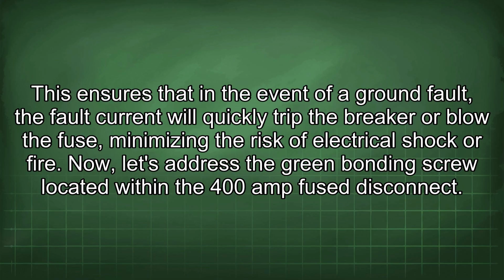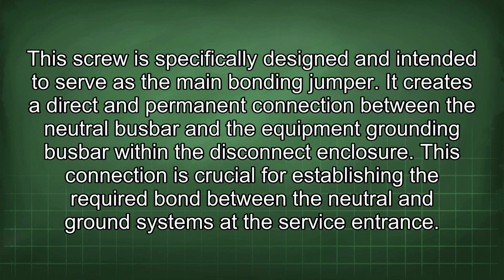Now, let's address the green bonding screw located within the 400 amp fused disconnect. This screw is specifically designed and intended to serve as the main bonding jumper. It creates a direct and permanent connection between the neutral busbar and the equipment grounding busbar within the disconnect enclosure. This connection is crucial for establishing the required bond between the neutral and ground systems at the service entrance.